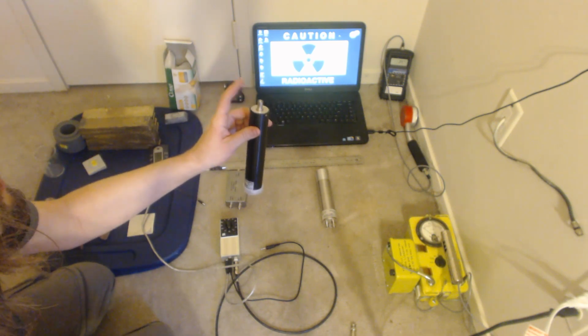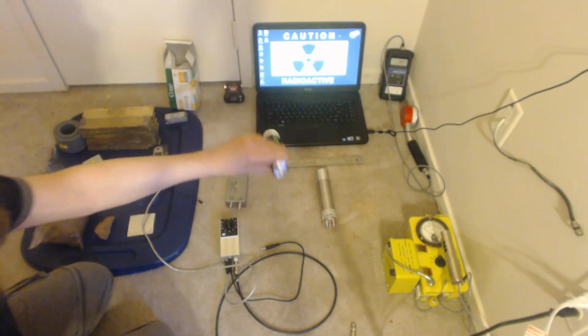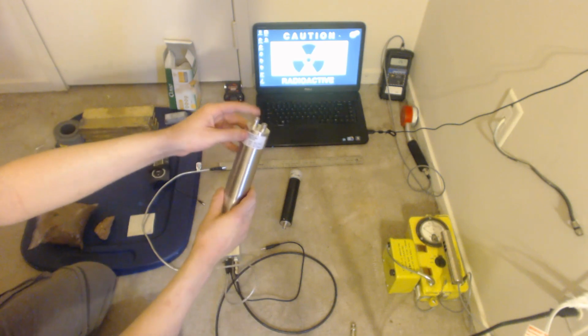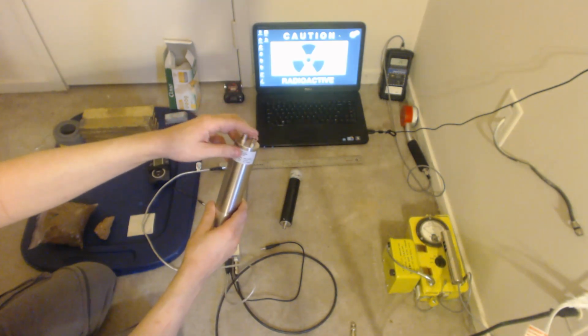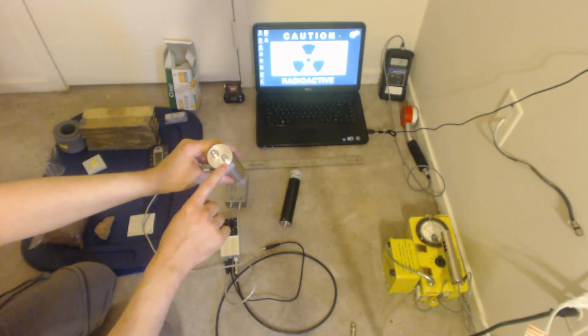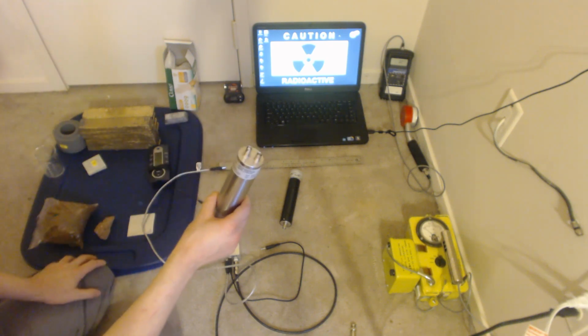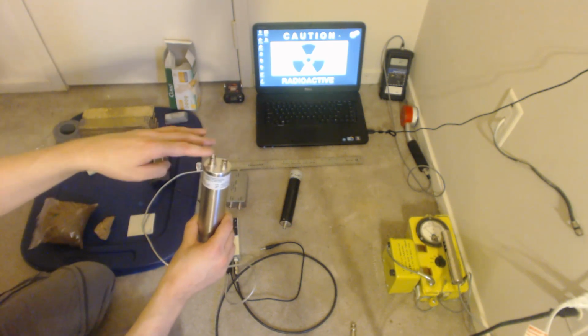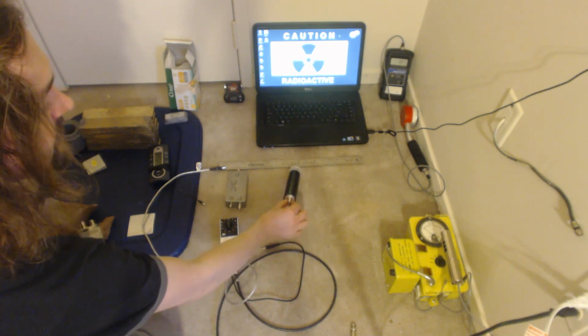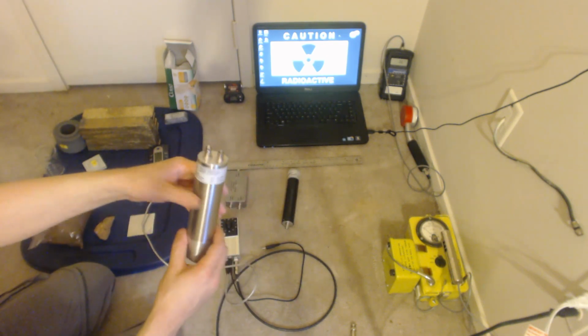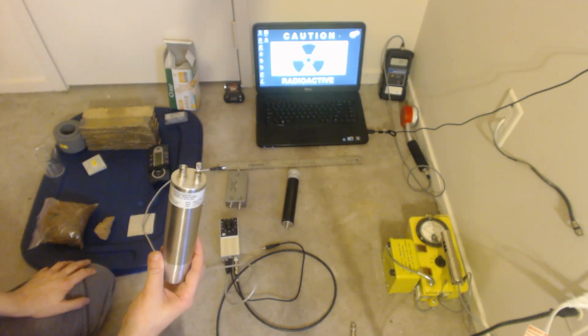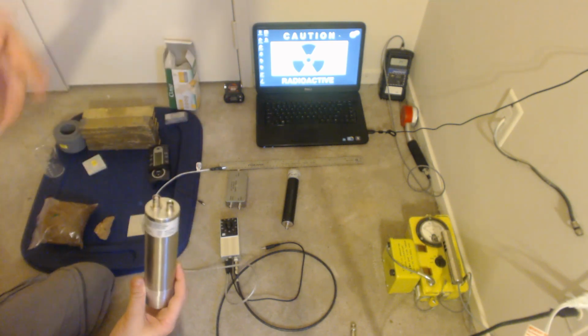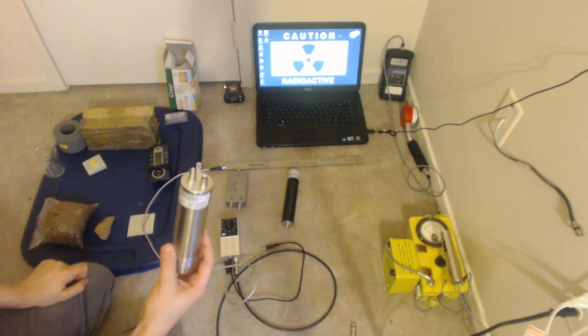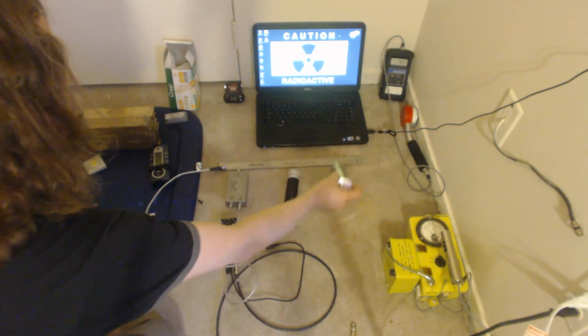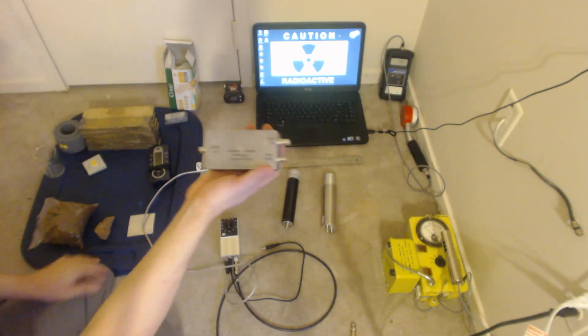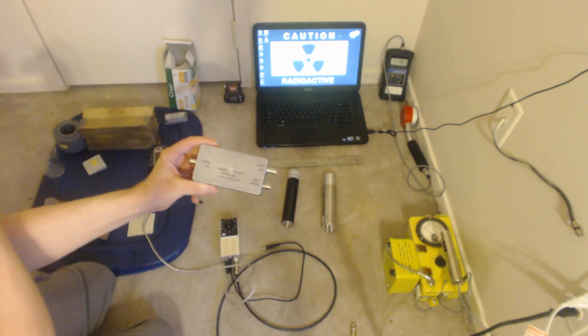You're going to end up getting a single connector that has signal and power together, or you're going to end up with a dual connector which has signal and power separate. These types are usually lab grade units, which isn't to say that any unit like this isn't, but typically these are more like lab grade units. They separate the two because it's less noise. The two don't affect one another as badly. But when you buy one like this, you're going to need something like this. Two goes in, one comes out.